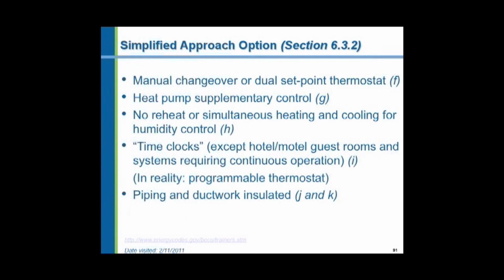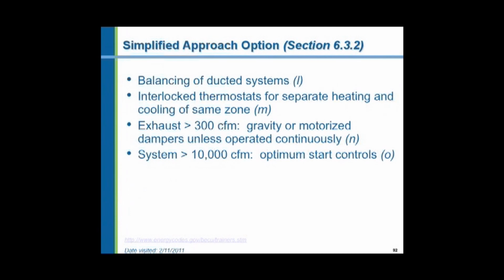Some of the other options are we have to have a dual set point thermostat or a manual changeover from heating to cooling to make sure that we do not do simultaneous heating and cooling. Don't have the furnace running at the same time as the air conditioner. Supplementary controls for heat pumps are covered. We cannot do simultaneous heating and cooling for humidity control. Time clocks are required. Basically, it goes on to describe in a big long paragraph the description of a programmable thermostat. So that is a requirement. The piping and the ductwork has to be insulated. The systems have to be balanced. They have to be adjusted after they're finished. The thermostats have to be interlocked.